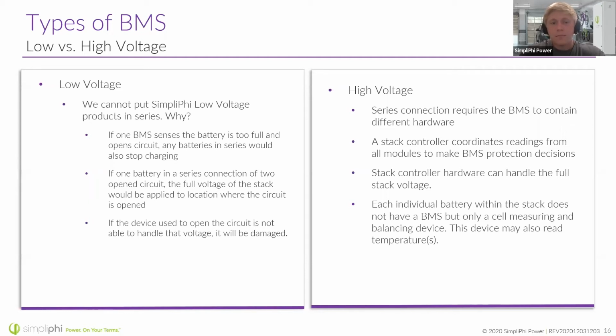In a high voltage battery system, however, a stack controller is used. The stack controller monitors each individual cell balancer or BMS within each individual battery pack, and it is the only device that would ever open or close the circuit. Therefore, it is designed to handle the full high voltage of the stack.